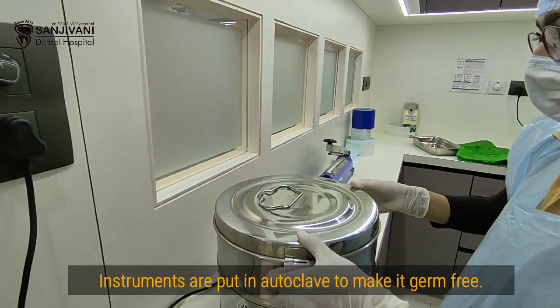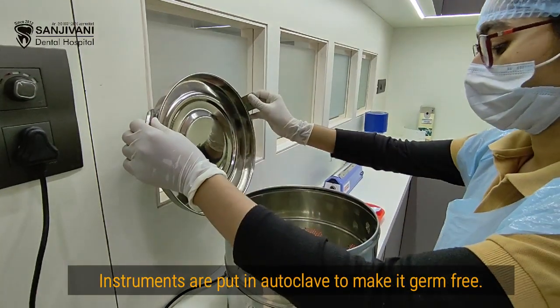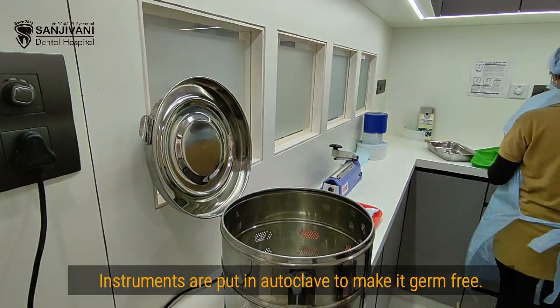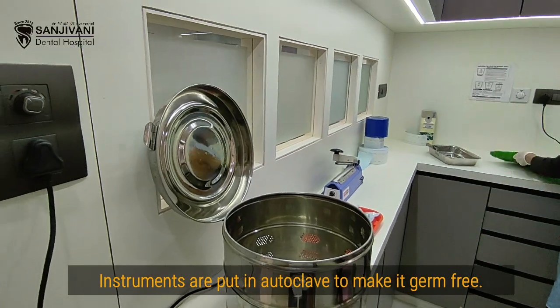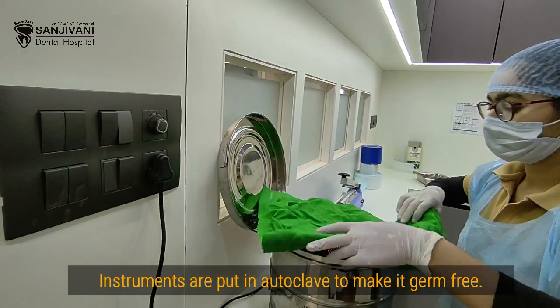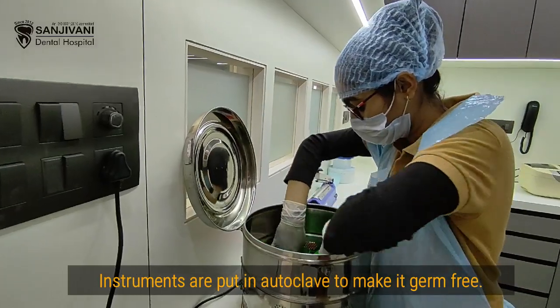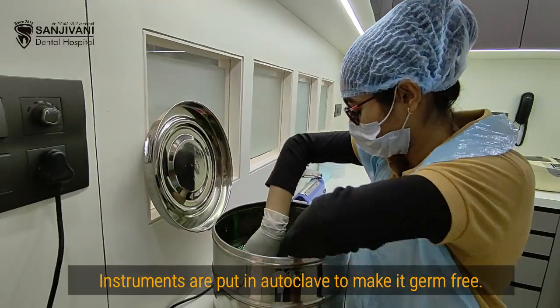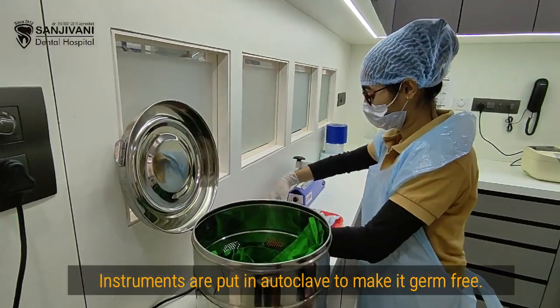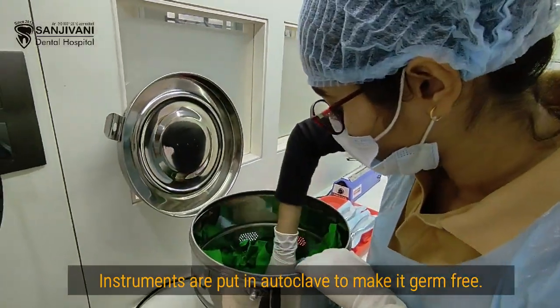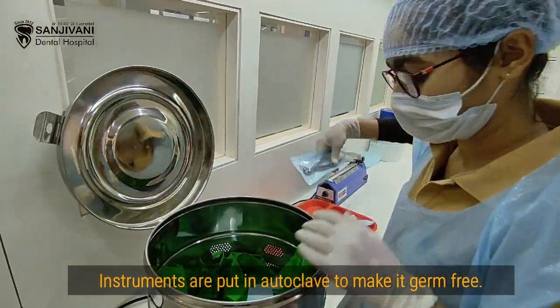All of these instrument pouches are now kept in an autoclave drum. Autoclave is the process which uses steam pressure of 15 psi at 121 degrees Celsius temperature to kill all the microbes and their spores and make our instruments germ free. The process of autoclave is carried out for 30 minutes.